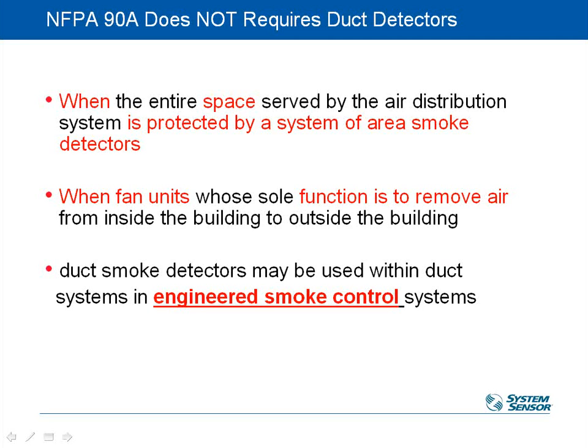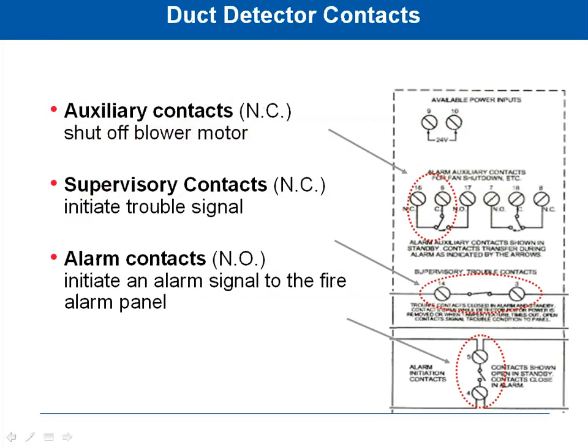You don't have to have them when the fan units have a sole function of removing air from inside the building to the outside, so an exhaust-only system. So if you have a straight exhaust system, like bathroom exhaust for a common 10-floor building or something, one common exhaust system, it'll be over 2,000 CFM, but you don't need duct detectors because it's not going to spread smoke throughout the building. Okay? Only systems that are recirculated will require duct smoke detectors. And then, of course, there's engineered solutions that might give you the ability not to have them as well.